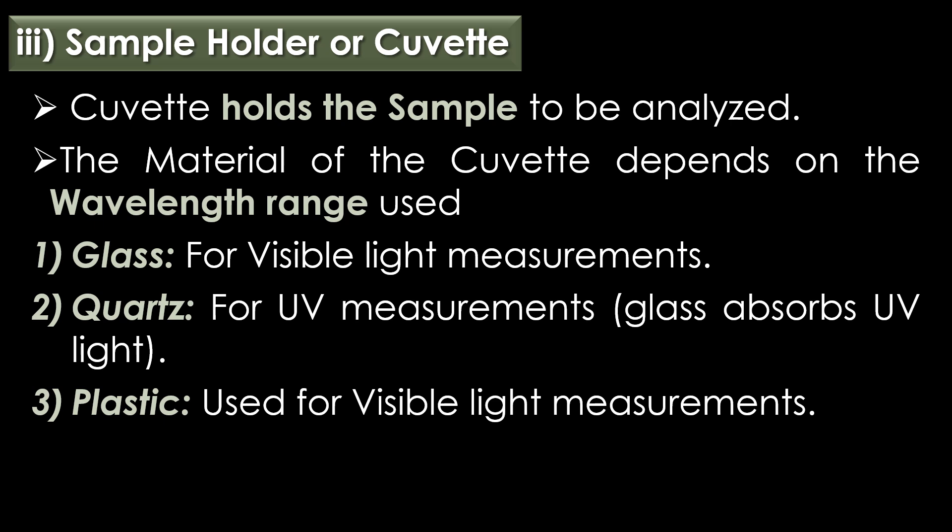Sample holder or cuvette: the cuvette holds the sample to be analyzed. The path length, typically one centimeter, is the distance the light travels through the sample and is a critical parameter in Beer-Lambert's Law. The material of the cuvette depends on the wavelength range used. Three types are used: glass, quartz, and plastic. The glass cuvette is used for visible light measurements, the quartz cuvette is used for UV measurements as glass absorbs UV light, and plastic is sometimes used for visible light measurements.